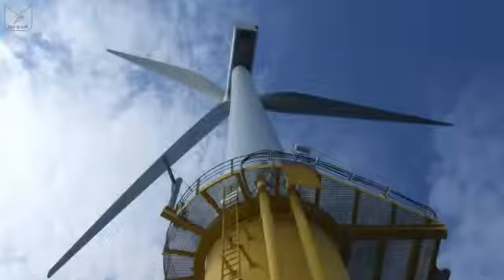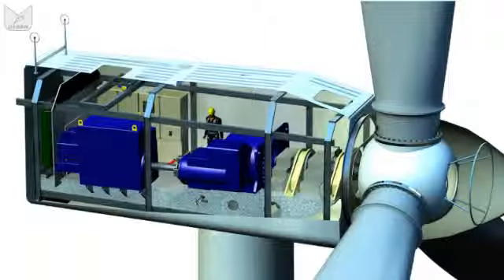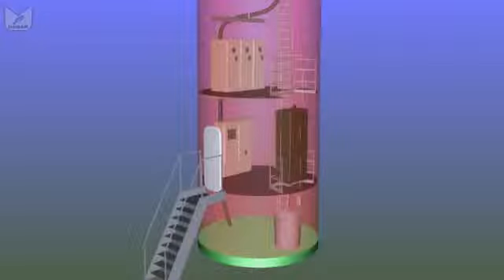Where we place the high-voltage transformers in multi-megawatt turbines is a lot more variable. Quite frankly, we have a lot more room, so we can decide. They can be in the nacelle, they can be at the base of the tower, they can be on platform 1 in the basement, they can be outside in a hut. In this example, the transformers at the top, so when we go into our door, the one thing we'll not find is a transformer.